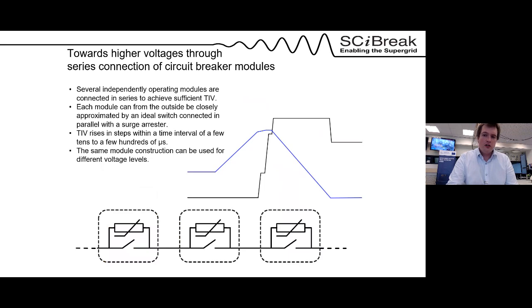A major design decision at SciBreak has been to divide the circuit breaker into many modules. There are several benefits to this approach. For instance, we can design one module, and then test that design very carefully, and then use that module to design breakers of various voltages.